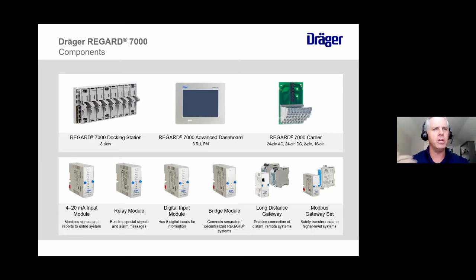But some of the flexibility you get with the Regard 7000. Some of the different modules we have available on the bottom: like I mentioned, we have a 4 to 20 input module, both regular and HART. We have a relay module, both regular and complex. We have a digital input module.